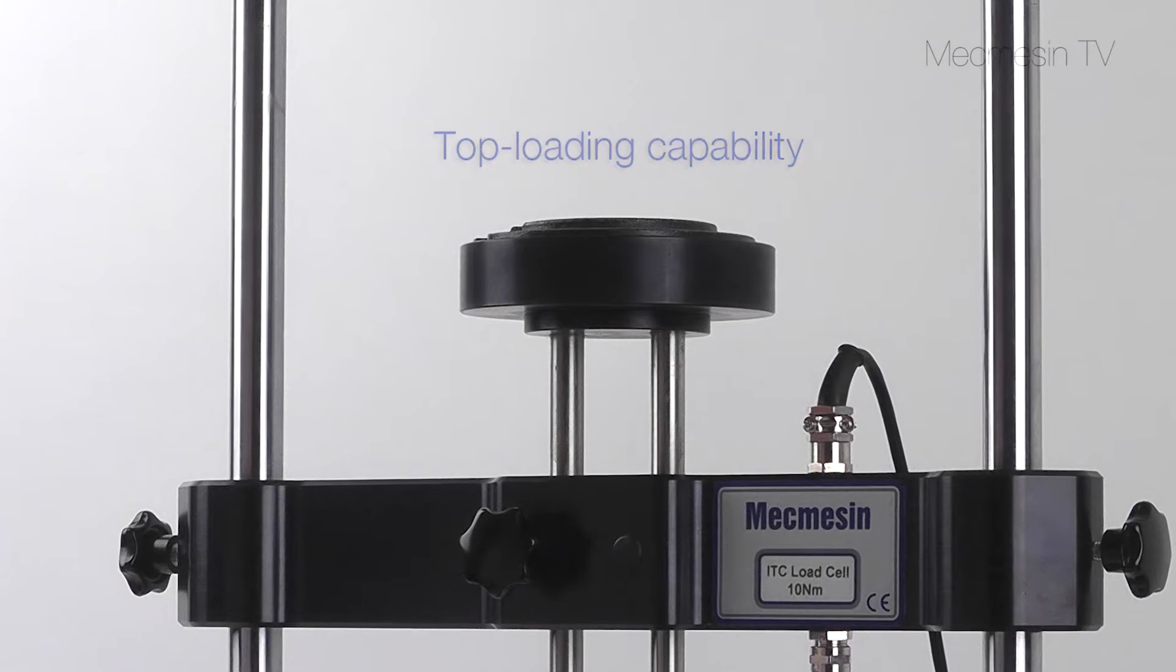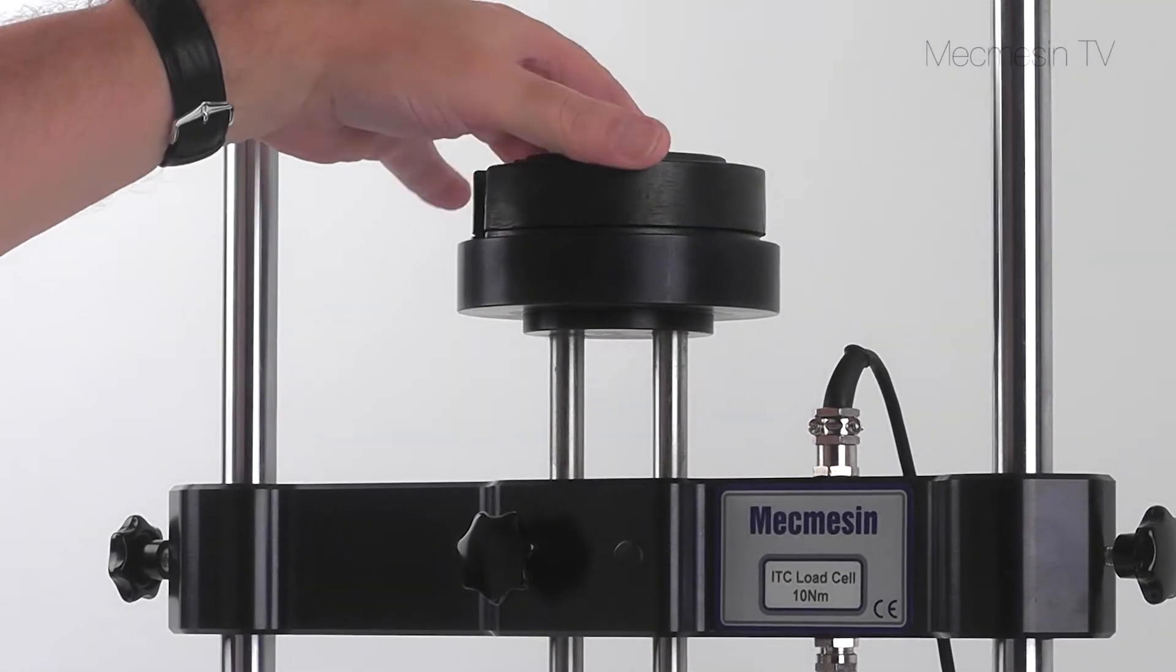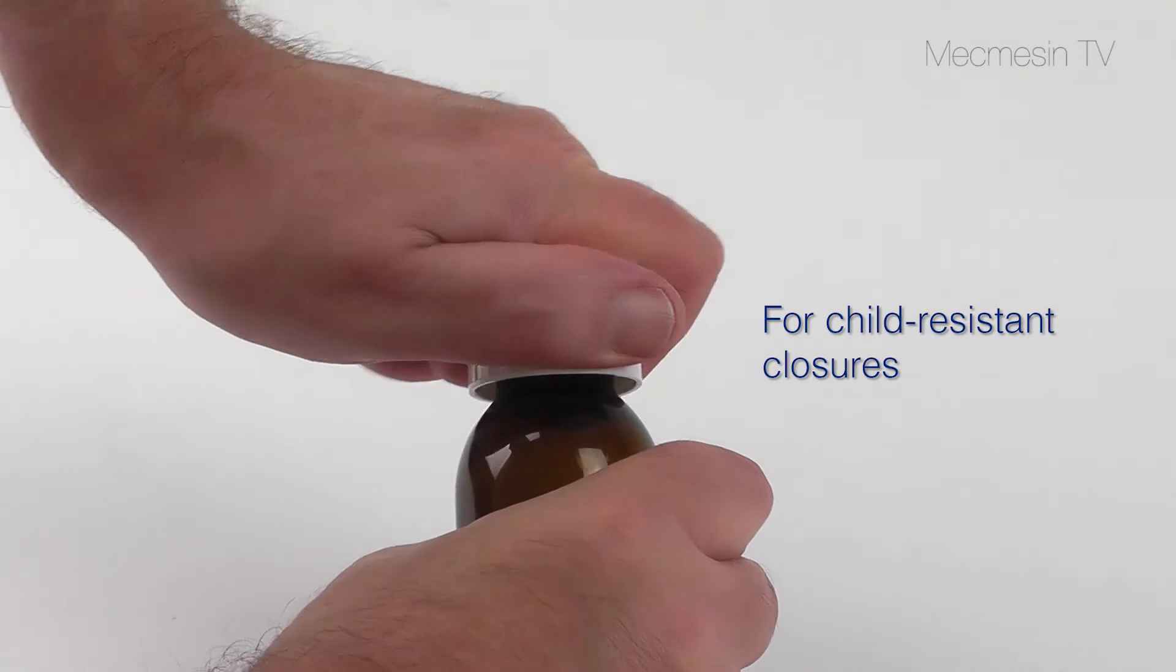A top-loading facility is available to provide a constant downforce, for example when measuring child-resistant closures.